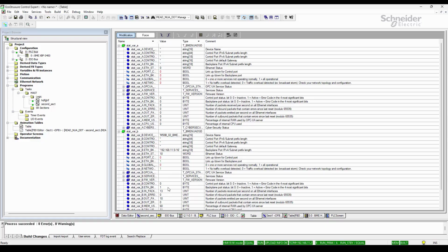So this video was to show you what caused the issue of the value stopping to be updated, which is because of the management array for the communication block that is causing an issue when it's being copied over from the primary to the standby. When you do a swap over, sometimes this is going to happen. We were lucky to see it on the first go. Sometimes it might take multiple times for it to happen, but it shows you.